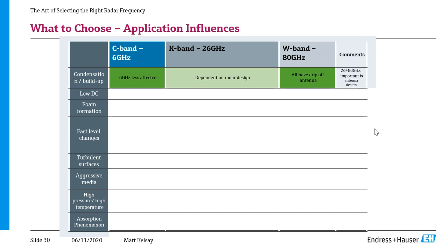I always relate this to a foghorn. A foghorn is a very low frequency and it penetrates through that fog, or what you could relate to steam or condensation, very well. So lower frequencies are less affected, but all of the lower frequencies have that big horn style. So typically in those applications, I would prefer to go to a higher frequency that has the flush mount style design. For low dielectrics, with a higher frequency, you're going to get a longer measuring range and better performance. It's possible to measure in all of our frequency bands, but best to do with a high frequency.